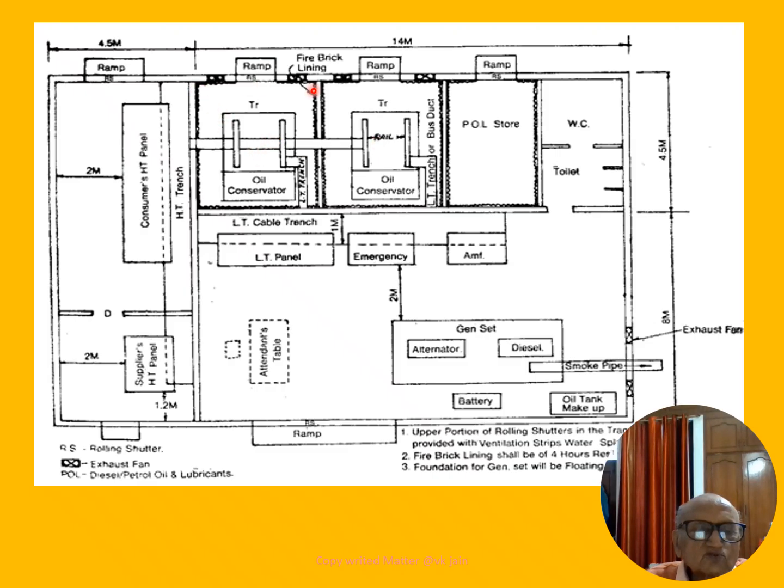This complete room is insulated by fire brick, and the transformer stands on a transformer foundation. These are the rails over which the transformer is mounted. And there may be another transformer similar to it. In cases of all this heavy electrical equipment, a ramp must be provided.